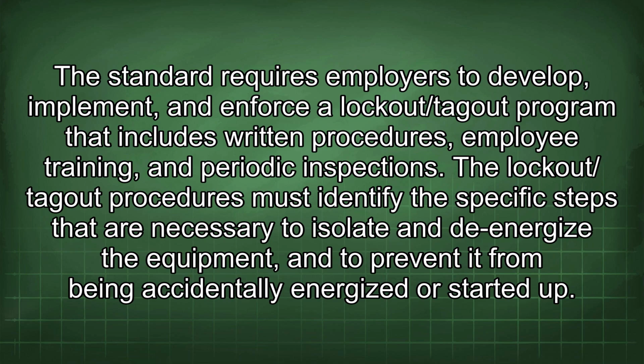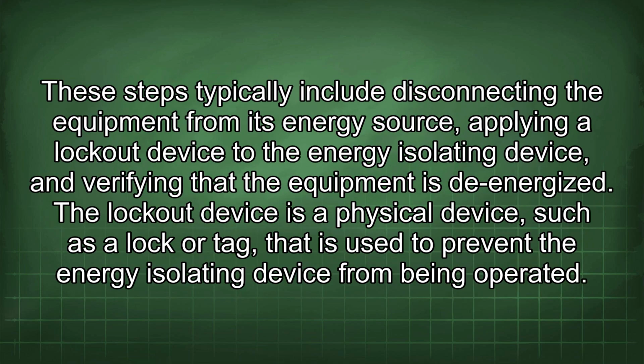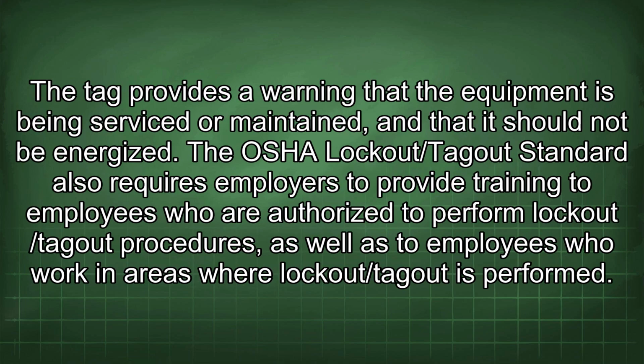and periodic inspections. The lockout/tagout procedures must identify the specific steps that are necessary to isolate and de-energize the equipment, and to prevent it from being accidentally energized or started up. These steps typically include disconnecting the equipment from its energy source, applying a lockout device to the energy isolating device, and verifying that the equipment is de-energized. The lockout device is a physical device, such as a lock or tag, that is used to prevent the energy isolating device from being operated. The tag provides a warning that the equipment is being serviced or maintained and that it should not be energized.